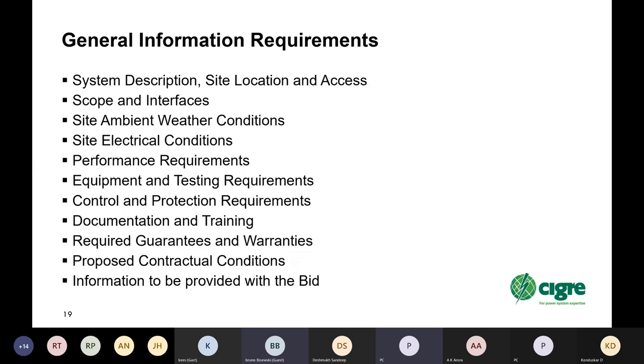So for the specification, what are the general information requirements? First, the system description, the AC system description, the DC system description, as already mentioned, the site location and access, scope and interfaces, already discussed, site ambient weather conditions, site electrical conditions, performance requirements, equipment and testing requirements, control and protection requirements, documentation and training requirements, required guarantees and warranties, contractual conditions, and then usually tables are provided so that technical information can be provided by the bidders, so that when you're reviewing the bid, you can make a decision based on the quality of the equipment being provided.